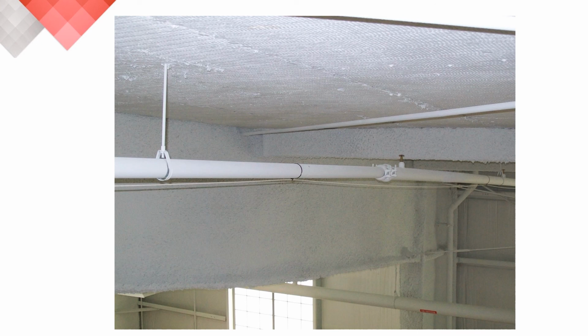Earlier in the presentation, we discussed installing Protectowire on ceiling sprinkler pipes. This is a good image of that. You find that the detector is appropriately supported by the double loop pipe straps with a small amount of sag. The detector is not hanging overly low or pulled too taut.